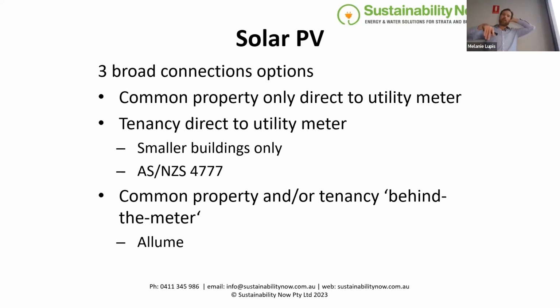But there's a good way around that, called Allume — you've probably heard of it. It's a special box that lets you put a very big solar system up there with just one inverter. So you might have a 50 kilowatt system with one inverter feeding into this Allume box, which then distributes it to each tenancy. That gets you around the 30 kilowatt limit — you only need one grid protection relay, and it's all done behind the meter. It is quite expensive though.